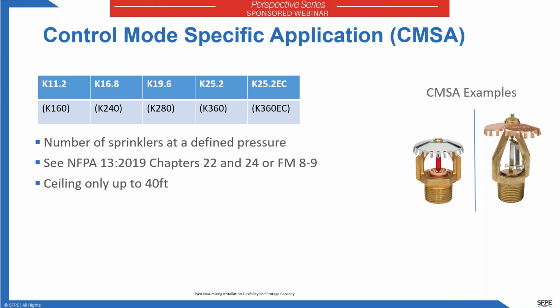The installation requirements for CMSA sprinklers specify the maximum distance and minimum distance between sprinklers, which essentially defines the area that sprinklers can protect. But the hydraulics are only based on numbers of sprinklers at a defined pressure. Looking at protection schemes for CMSA sprinklers, again depending on storage arrangement and commodity classification, you could have ceiling-only protection schemes up to about 40 feet in height.